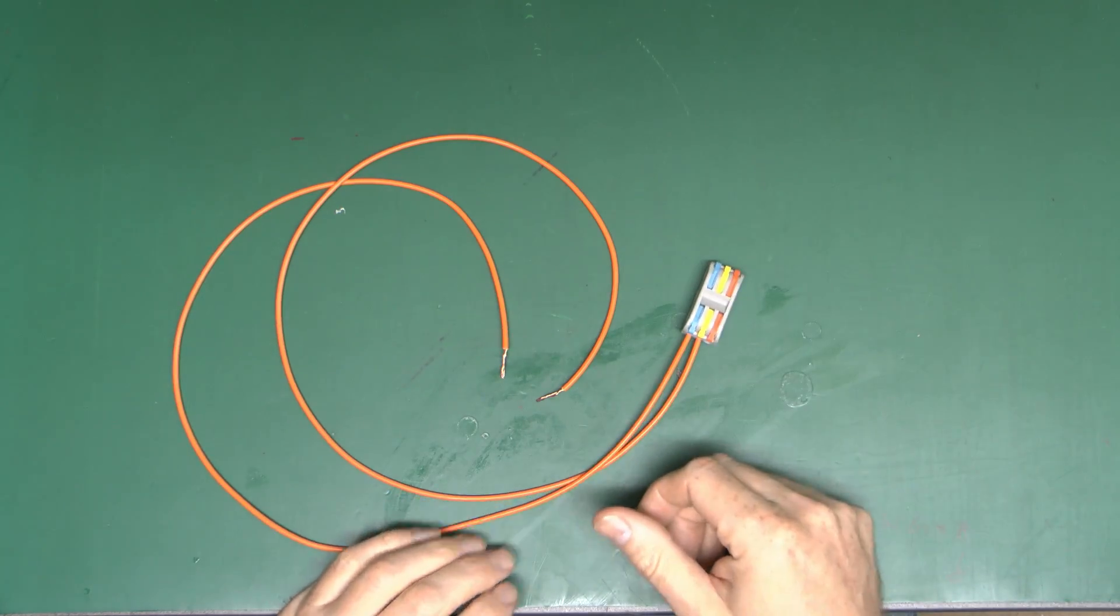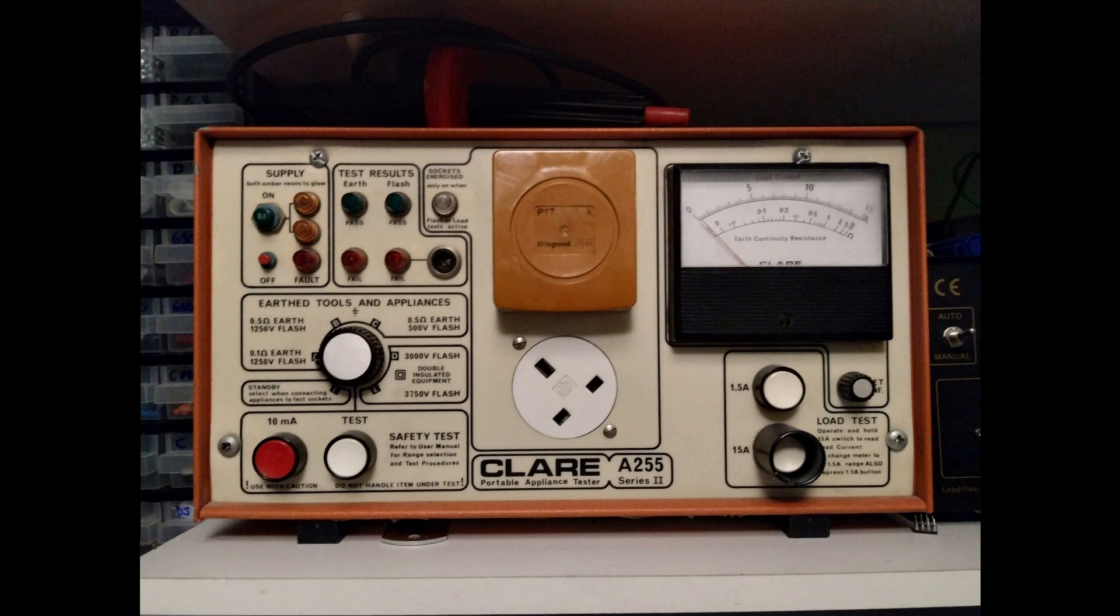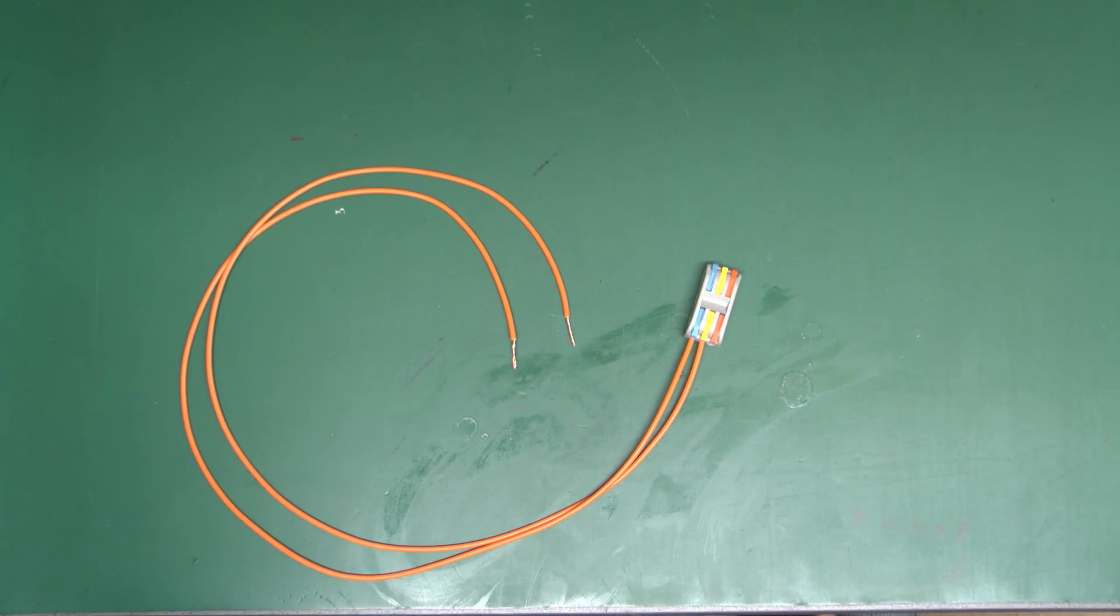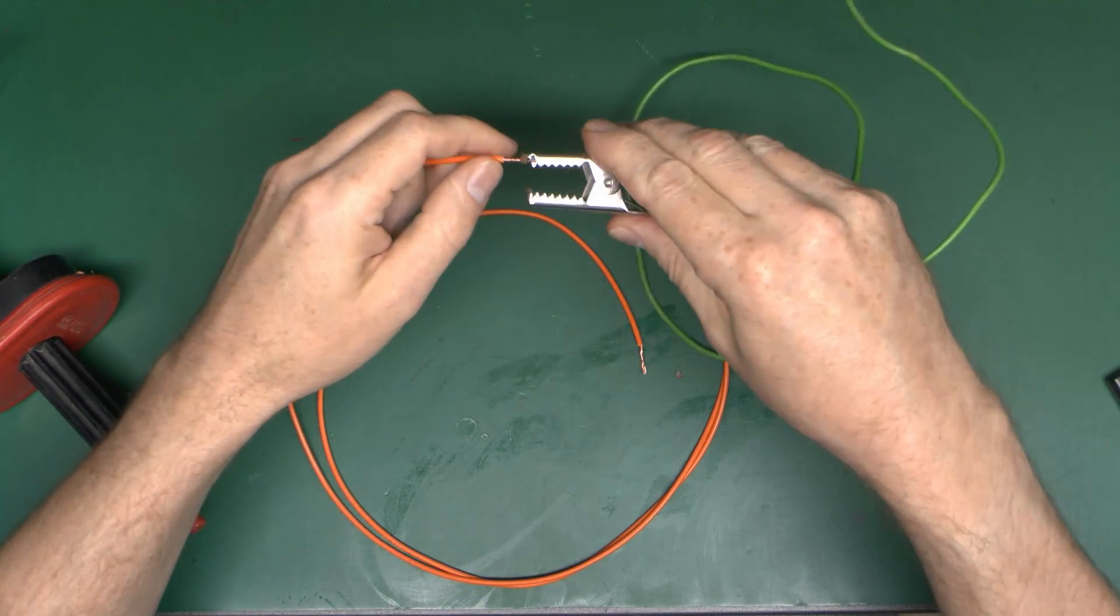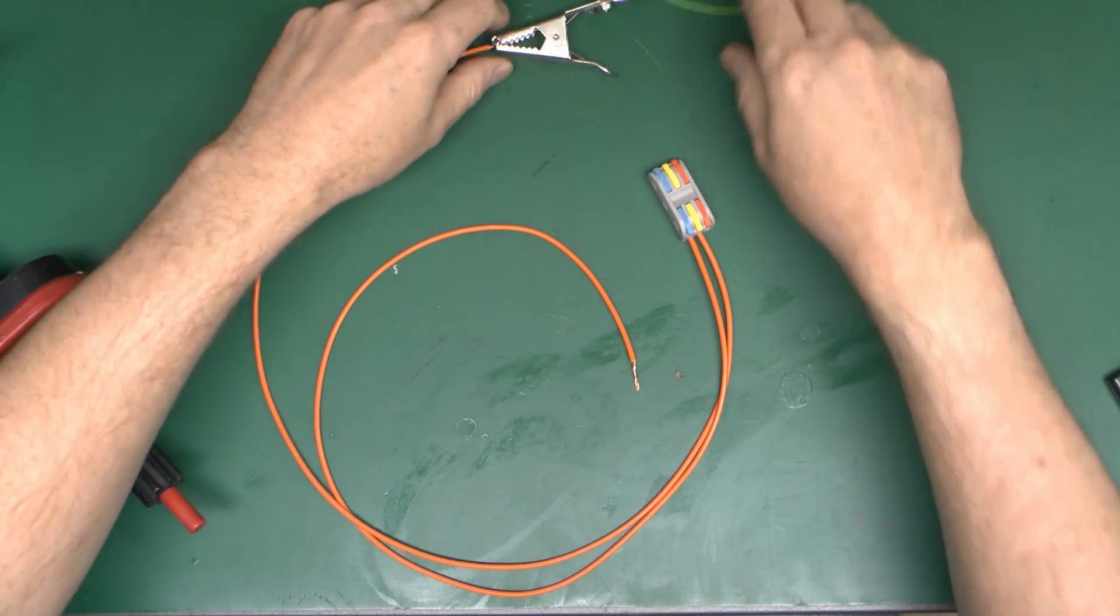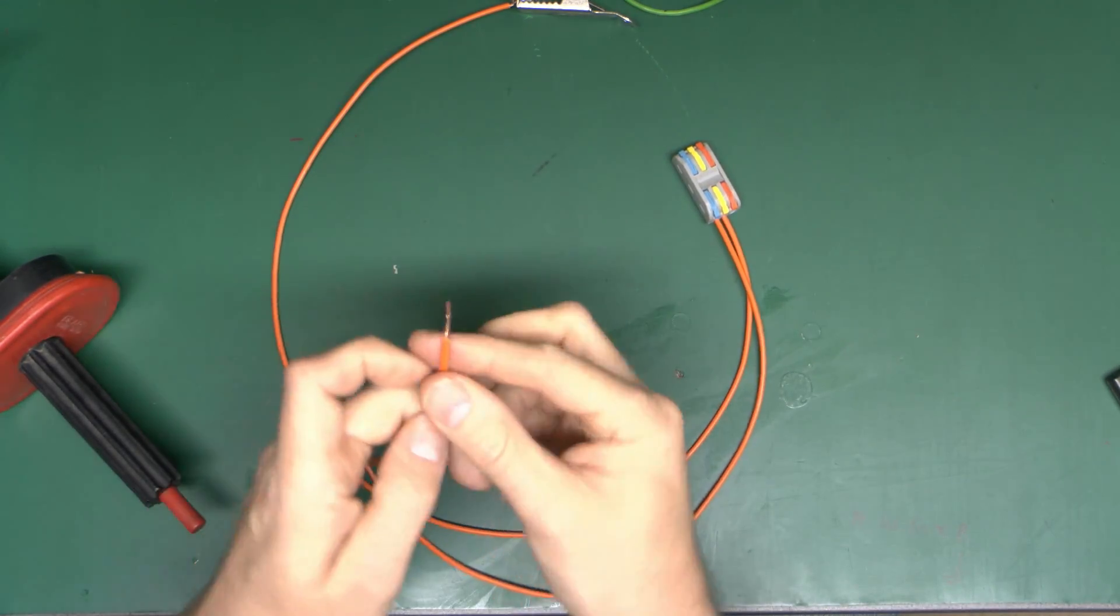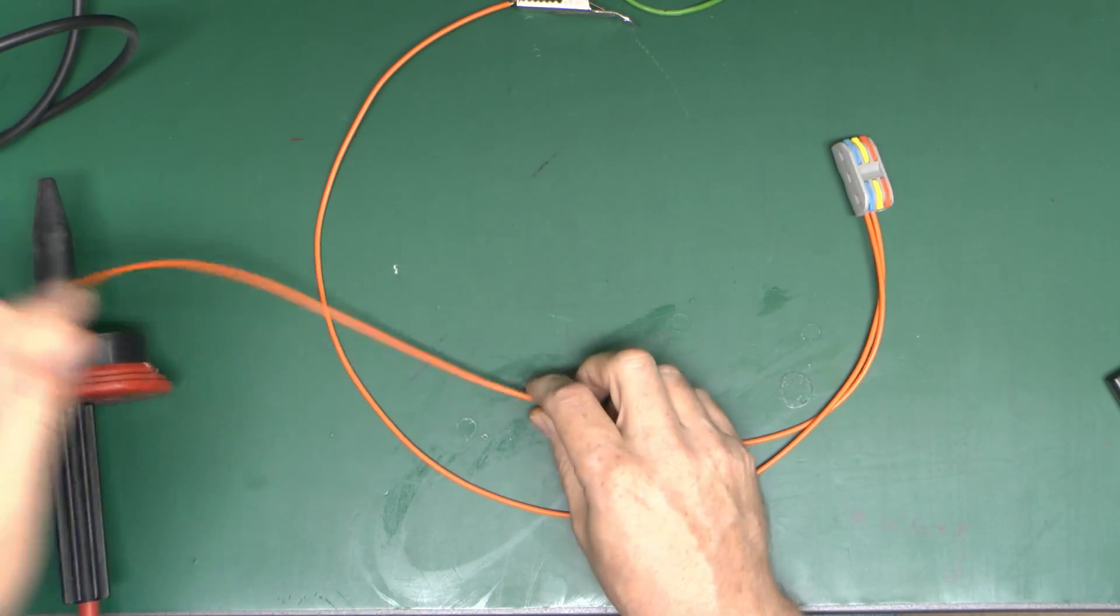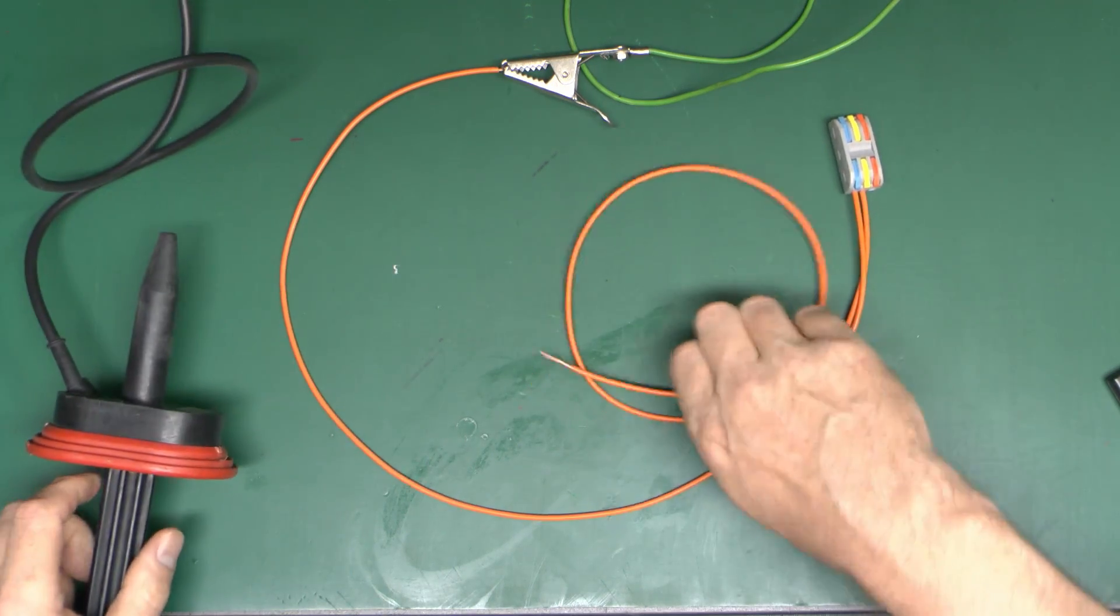However, of course, that's not really good enough, because let's see at what level these things would actually fail. So what we can use is this device up on the shelf here, which I can't actually show in shot with this at the same time as the other, but I've seen it before. And essentially this can generate voltages of somewhat more than that. We've got a 1250 option, and most interesting here we've got the 3000 option and also the 3750 option. So turn that on there. Now this isn't the actual intended use for this machine, but it will do the job in this particular case. So what we want to basically do is to connect this wire here, which would normally connect it to the metal parts of the equipment, and is actually connected through to the earth pin on the appliance there. And then we'll connect the other end to this. And the other end happens to be this high voltage probe, because obviously we don't want to be touching that with 3000V at the end of it.